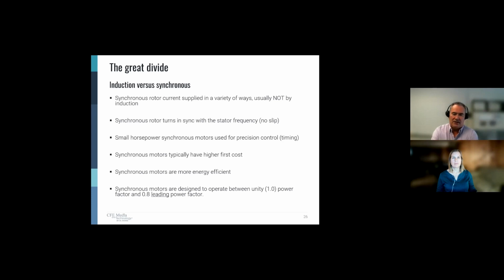Synchronous motors of any significant size typically have a higher first cost, which is why we don't see a lot of them. They're more energy efficient, however. So if we stop and think about the total cost of ownership, maybe we can overcome that first cost and use a synchronous motor. The big advantage is they're designed to operate between unity power factor and a leading power factor. So this is an opposite to an induction motor, which we can take advantage of. And we'll talk about that moving forward.